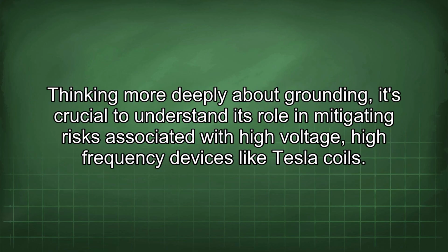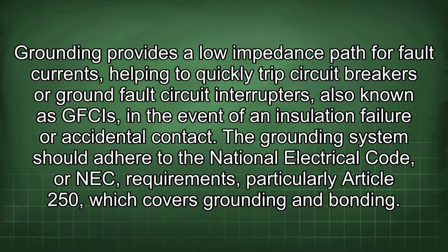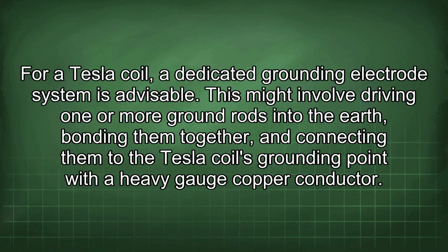Thinking more deeply about grounding, it's crucial to understand its role in mitigating risks associated with high-voltage, high-frequency devices like Tesla coils. Grounding provides a low-impedance path for fault currents, helping to quickly trip circuit breakers or ground fault circuit interrupters, also known as GFCIs, in the event of an insulation failure or accidental contact. The grounding system should adhere to the National Electrical Code, or NEC, requirements, particularly Article 250, which covers grounding and bonding.